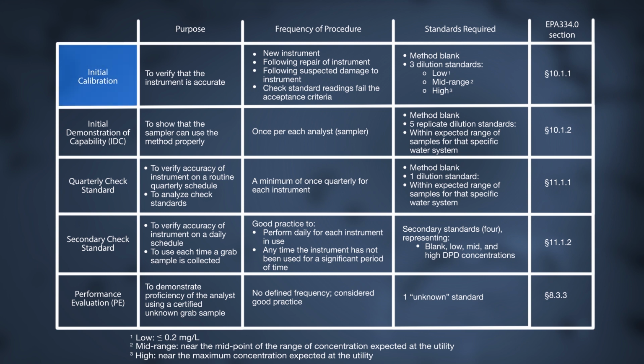Initial calibration. This is a procedure that uses diluted calibration standards to ensure the accuracy of the instrument. When obtaining a new instrument, or after a repair of an instrument, samplers must verify the internal factory-programmed calibration curve for grab sample instruments prior to placing the instrument into service. Initial demonstration of capability, or IDC, is a procedure to assess the ability of the analyst to generate acceptable precision and accuracy. The IDC must be successfully performed prior to analyzing any field samples. Quarterly check standard verification. Requires preparation and analysis of diluted primary standards once every 3 months.